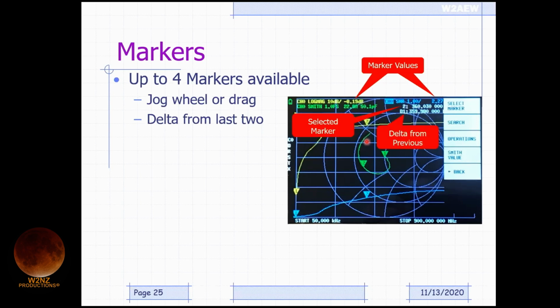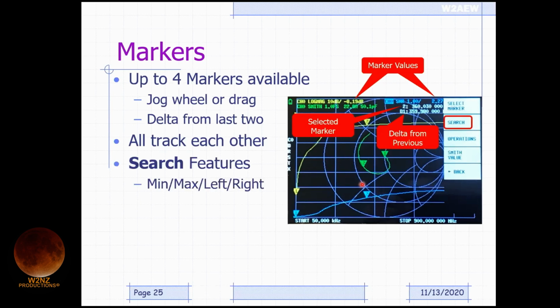minus 8.19 dB. With a lot of these devices, you can put up a second marker, and once you do, you essentially get a delta. What the delta shows is the difference from the previous marker that was active. In this case, the previous marker was 1, so there's my marker 1 down here. This D1 is showing me the delta, in this case the delta in frequency between those two markers. All the markers track each other on all the different traces, in that they'll all be at the same frequency. So the channel 1 marker is at the same frequency on all the traces that are active.